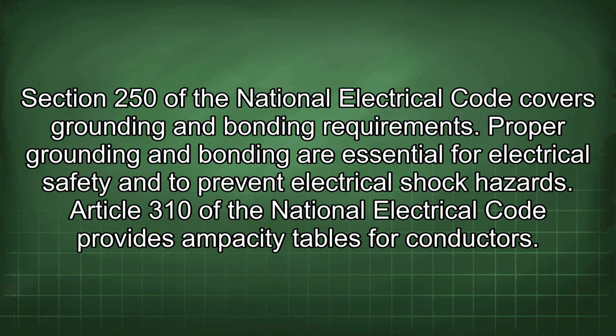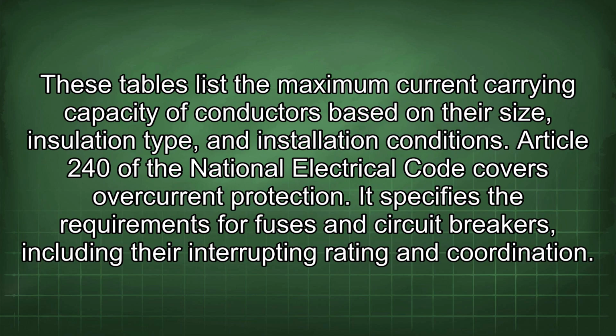Article 310 of the National Electrical Code provides ampacity tables for conductors. These tables list the maximum current carrying capacity of conductors based on their size, insulation type, and installation conditions. Article 240 of the National Electrical Code covers overcurrent protection. It specifies the requirements for fuses and circuit breakers, including their interrupting rating and coordination.